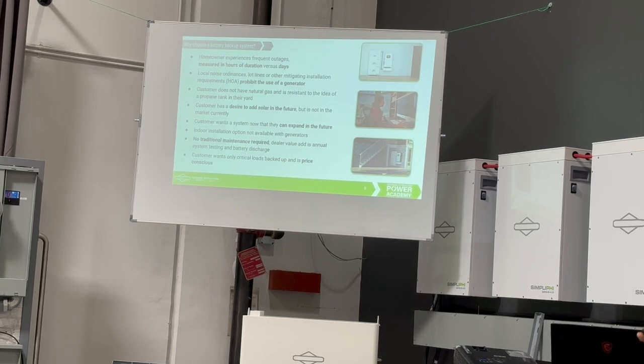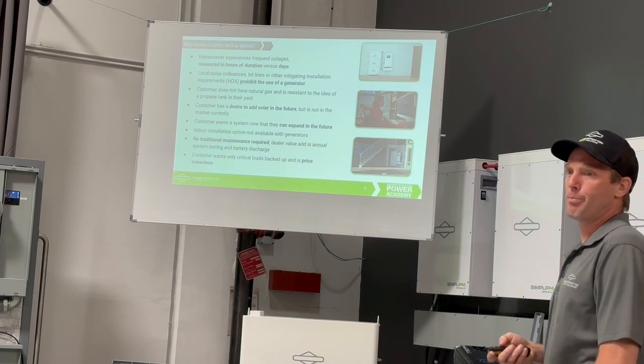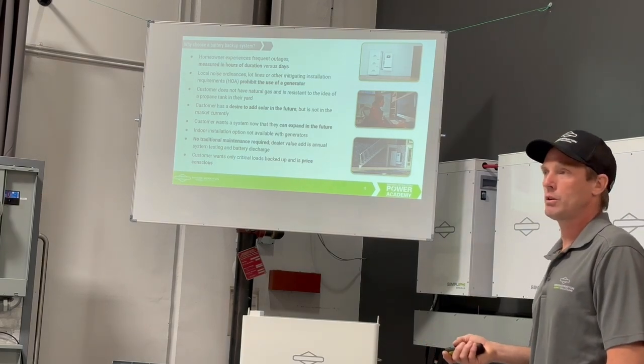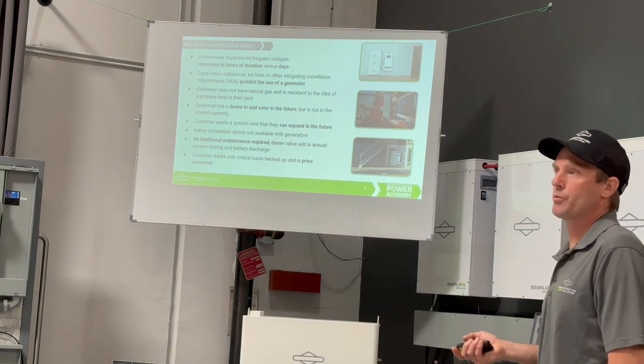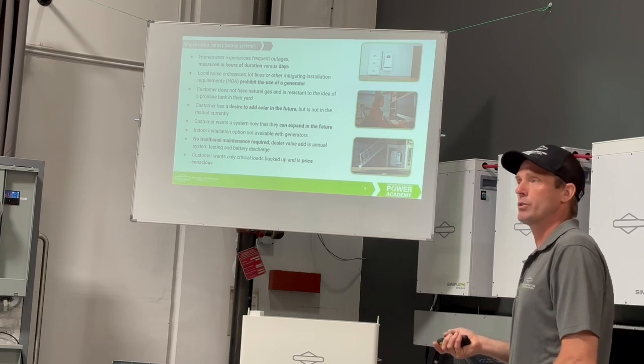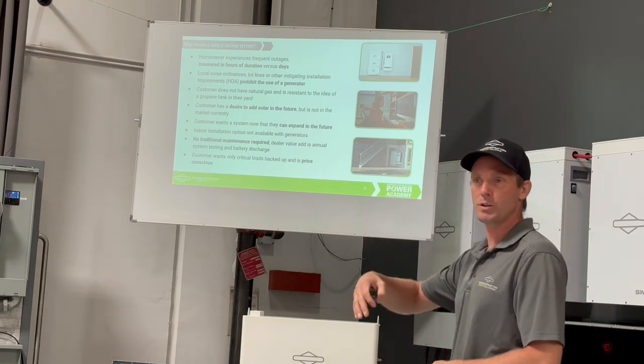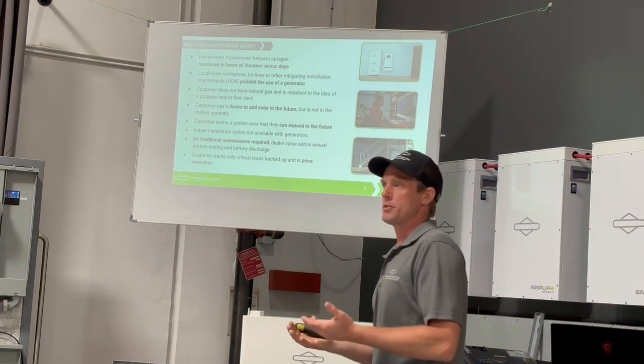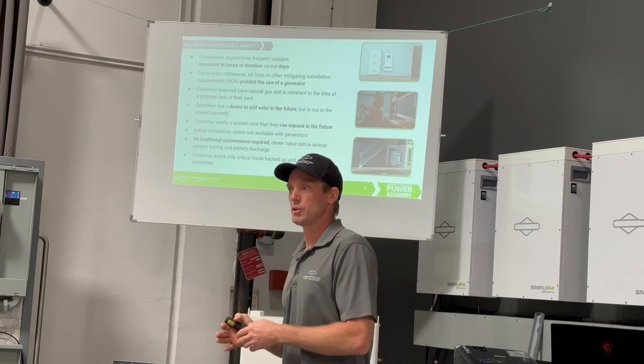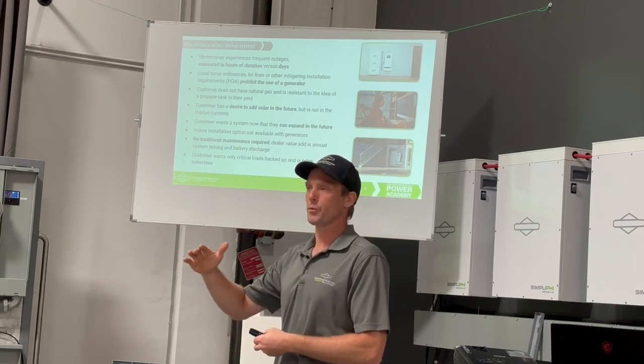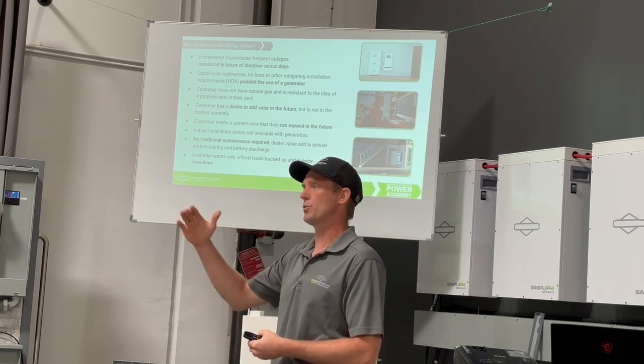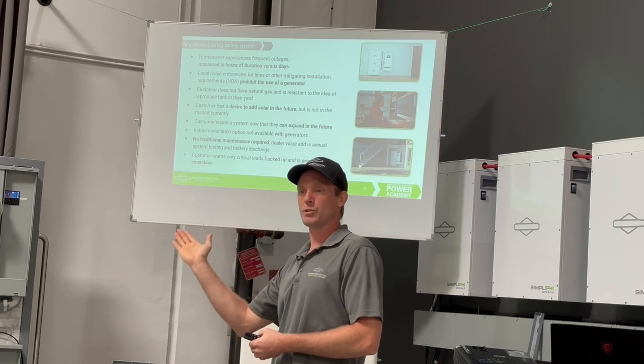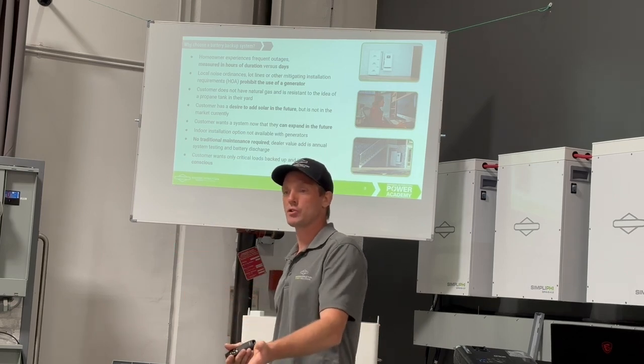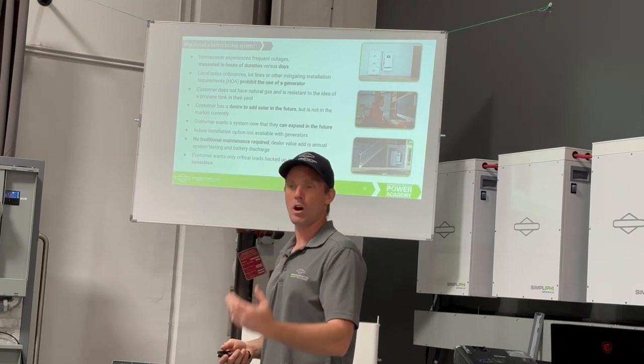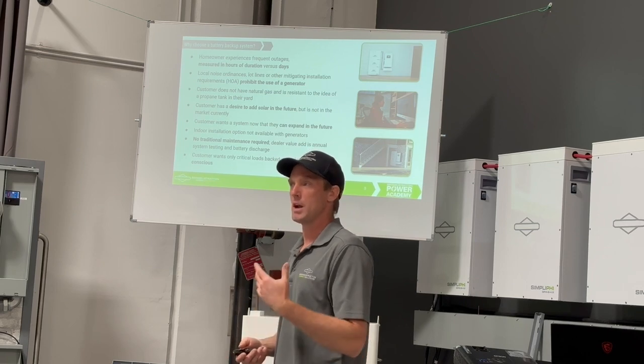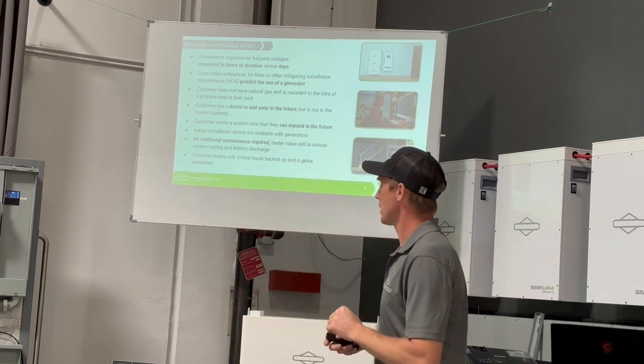One reason might be: if you're getting frequent outages that don't last very long, a battery system is a great option because you have uninterrupted power. Unlike a generator, when you lose utility power, the generator takes a little while to start up—it has to run for at least 60 seconds for the signal to qualify before it switches over. Meanwhile, the internet connection goes down, the clocks in the house need resetting—you lose power momentarily.